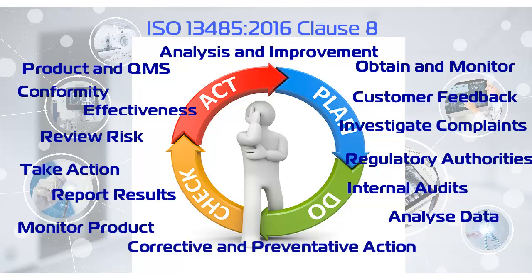The organization has to plan and conduct internal audits to determine whether the QMS is in conformity and processes are achieving planned results. You have to monitor and measure product during the manufacturing process to identify non-conforming product and take appropriate action to isolate such product and prevent unintended delivery or use. Finally, you are required to analyze data about your organization's QMS in order to evaluate its suitability and effectiveness and improve where indicated. Where appropriate, you need to take corrective and preventative action in order to maintain QMS suitability, adequacy and effectiveness and ensure medical device safety and performance.